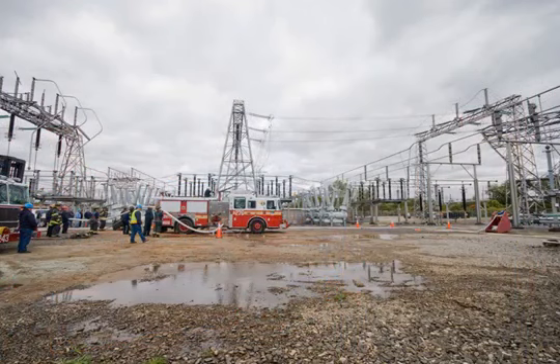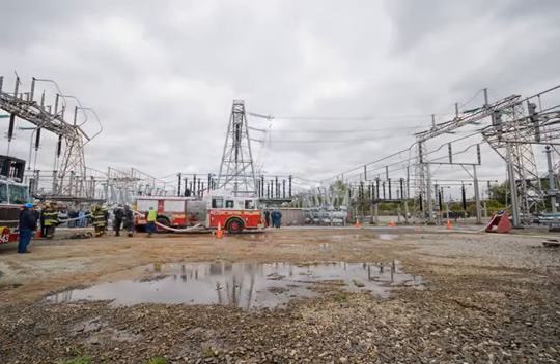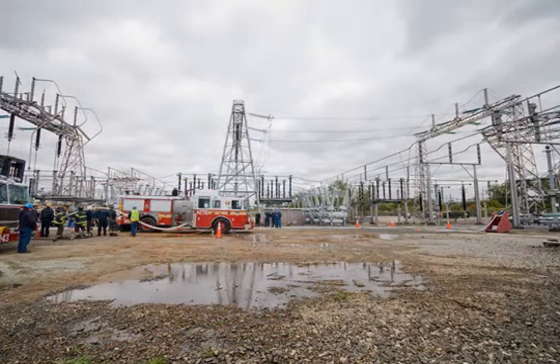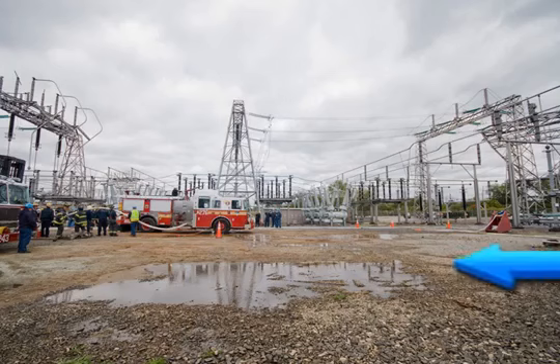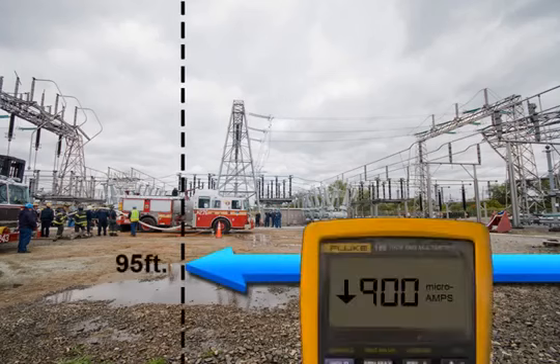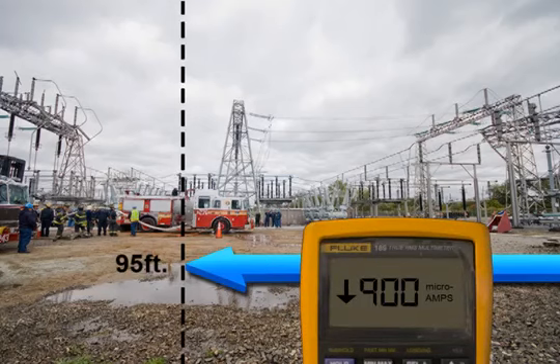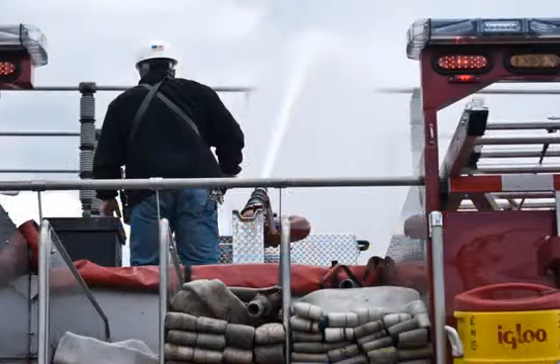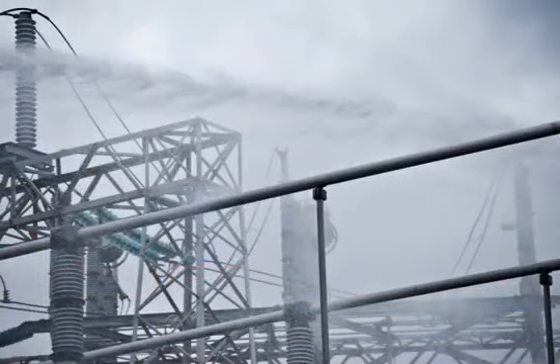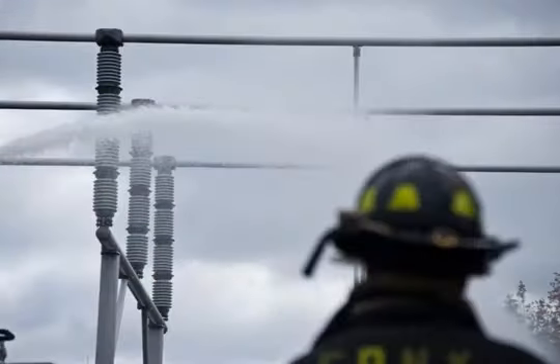At that point, we began to back up from the conductors in 10-foot increments until the current leakage values dropped to the acceptable threshold. At 95 feet, the current dropped below the safety target of 0.9 milliamps. We have now established a safe standoff distance for this delivery process.